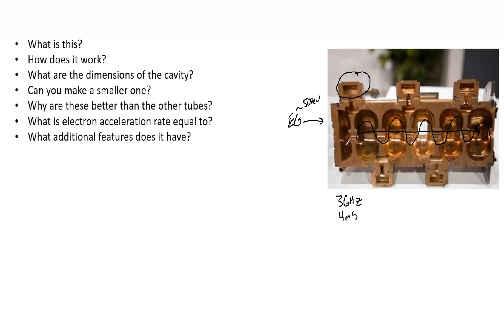Each dimension of the cavity is about 5 cm, and yes you could use a higher frequency like a 9 gigahertz X-band compared to the 3 gigahertz S-band that we use. So for example, like the CyberKnife, it uses this and it has a 3.3 cm cavity. So you can change the frequency and make a smaller one if you choose.